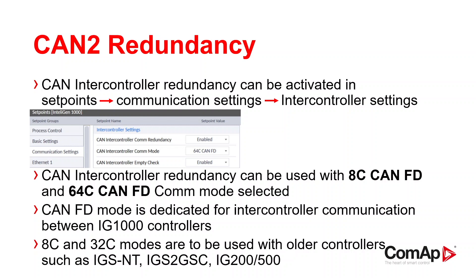CAN intercontroller redundancy can be used with 8C CAN FD or 64C CAN FD COM mode selected. CAN FD mode is dedicated for intercontroller communication between IG1000 controllers. The other two options, 8C and 32C modes, are to be used with older controllers such as IGSNT, IGS2GSC, IG200, or IG500.